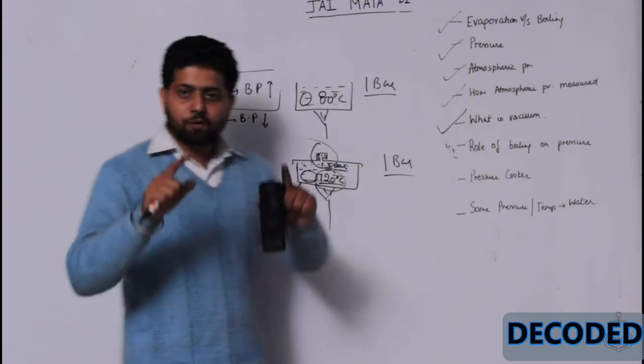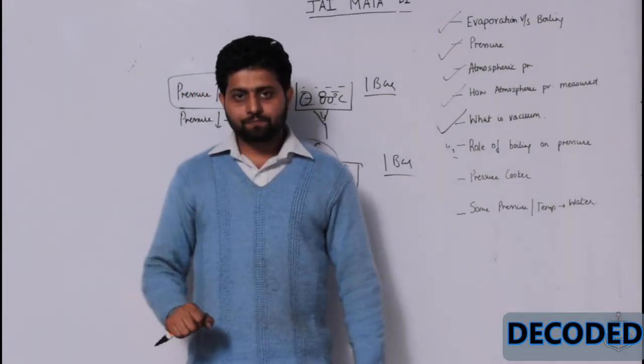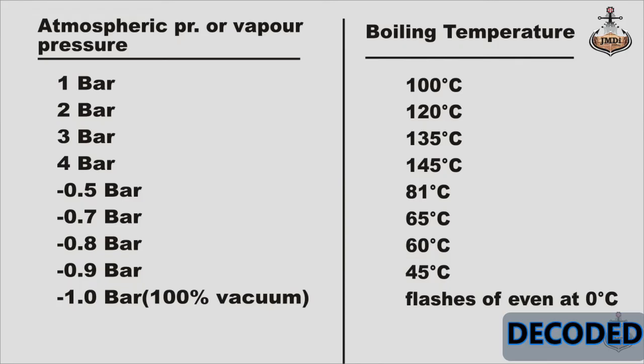So now, you have got a chart in front of you. You can see on the slide. At 1 bar atmospheric pressure, boiling temperature is 100 degree centigrade. At 2 bar, it is 120 degree centigrade. At 3 bar, approximately 135 degree centigrade. At 4 bar, approximately 145 degree centigrade temperature.